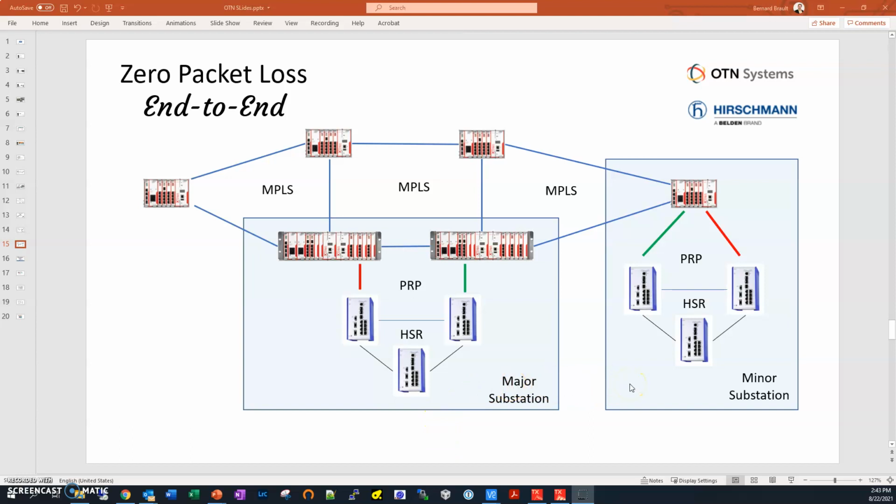So what I want to show you now is if, for example, you were to do inter-substation GOOSE messaging. Today you're using mirrored bits to send transfer trip, or you're still using transfer trips and current differential relay information between substations. In the future, that's going to be done through inter-substation GOOSE messaging, and these messages are so important that you don't have the luxury of retransmitting them in the traditional fashion, where it would be sub 50 milliseconds.